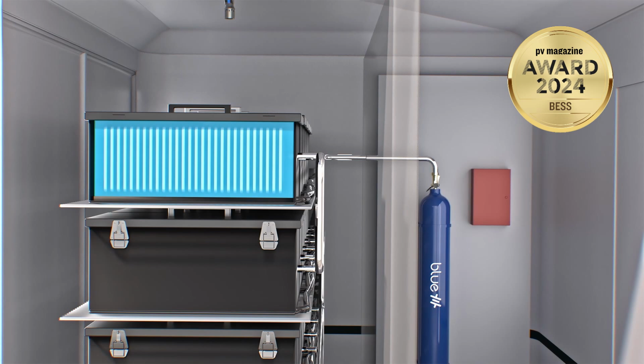With Fike Blue, what we look for is traditional detection methods. So smoke released, or gases released from the battery cell, could be hydrogen, or it could be optical smoke from when the thermal runaway event occurs. Fike Blue is then charged into a pipe network, and in the battery itself is a heat sensitive bulb. When the heat within the battery reaches around 58 degrees, the bulb will open and release Blue into the battery pack. What Blue then does is start to absorb the heat. Fike Blue has a very high heat capacity, with a boiling point of over 400 degrees. So it's sucking all the heat out of the initial cell going into thermal runaway, stopping it from setting the next cell off into thermal runaway as well.